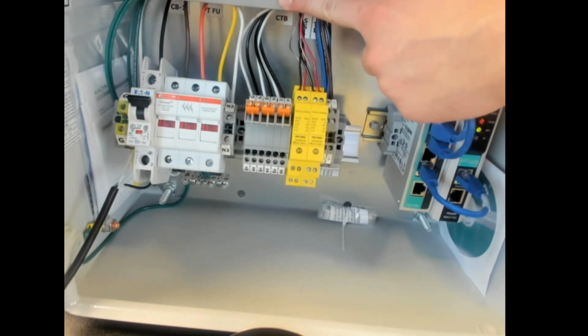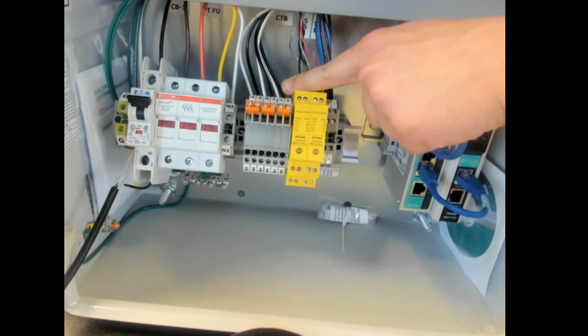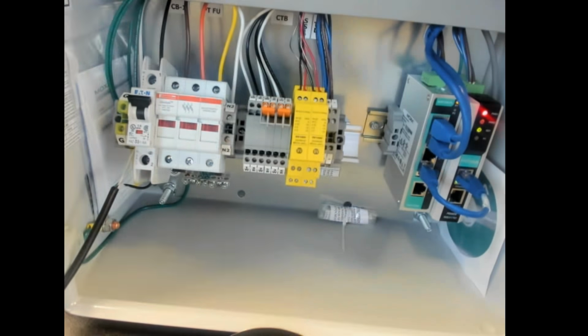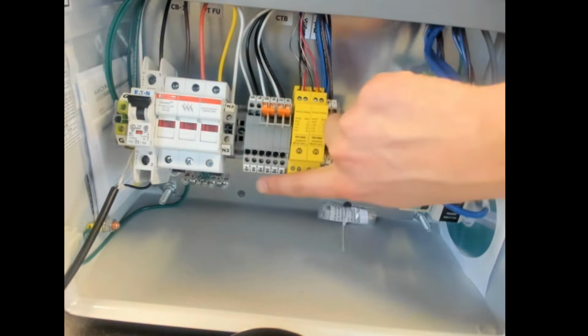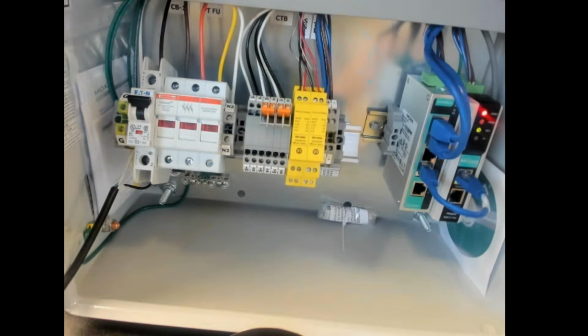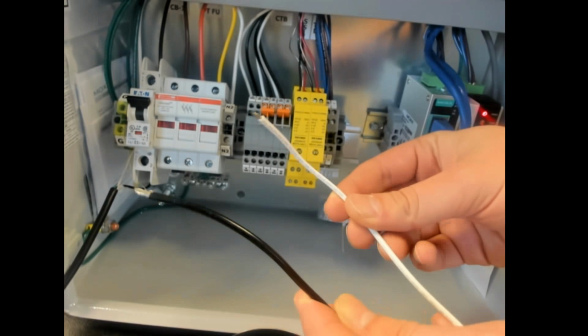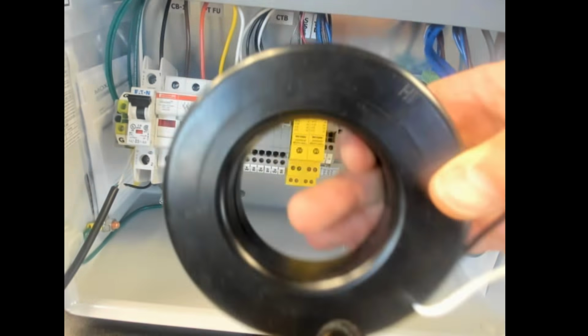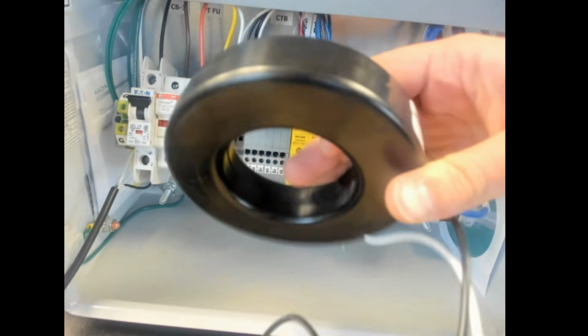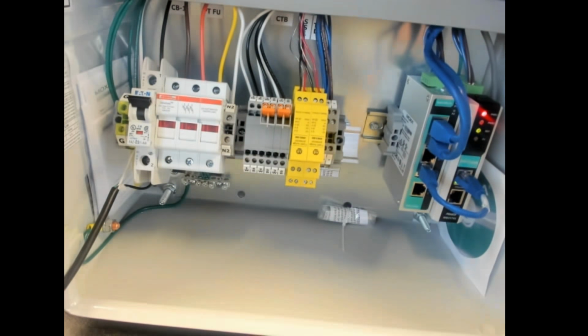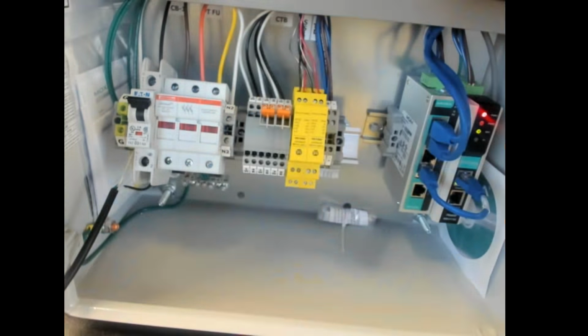Now, they could also electrically disconnect the top of the shorting block, I'm sorry, from the terminal block to the bottom by pulling this out. Now, that achieves the same safety, I suppose, in terms of no current flowing from the outside to the inside. But then what you have is these CT leads are not terminating anything. It's an open circuit. And you know, there are stories when you do this, basically what the CT does is it starts to shake. And it's not good. It'll start to break down mechanically. You'll obviously not have any measurements, and a lot of folks get confused about that. And it's obviously because there's no current flowing to the meter.